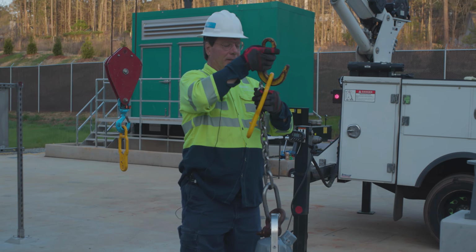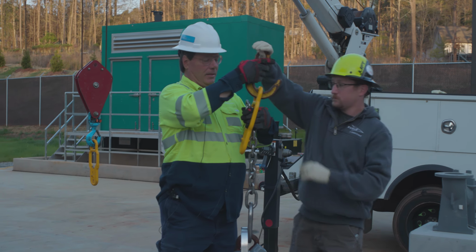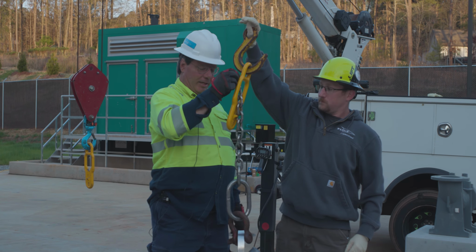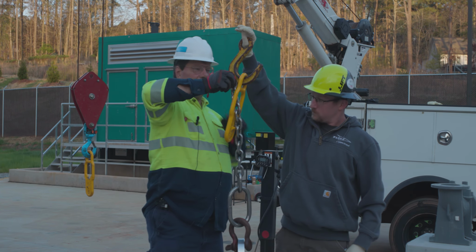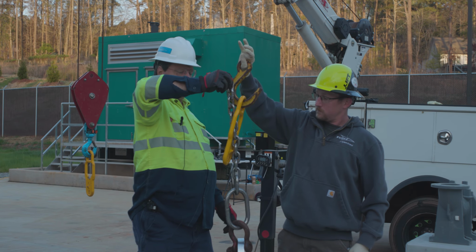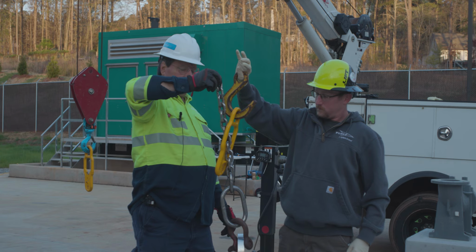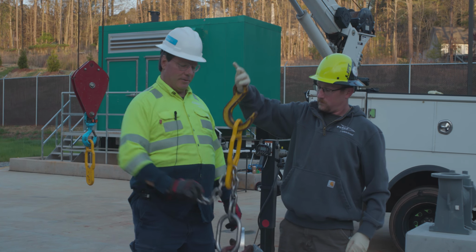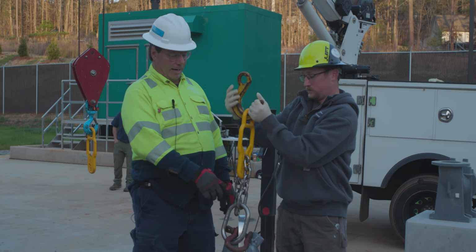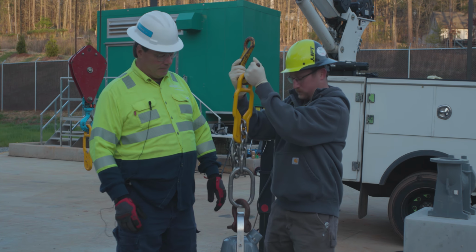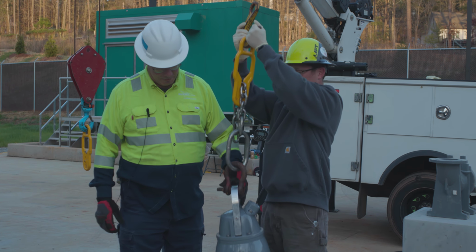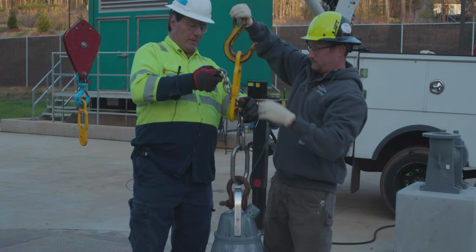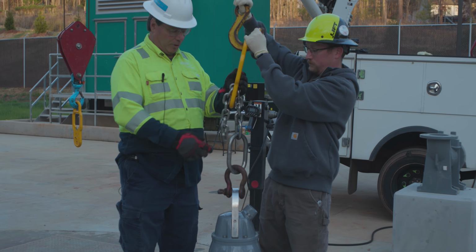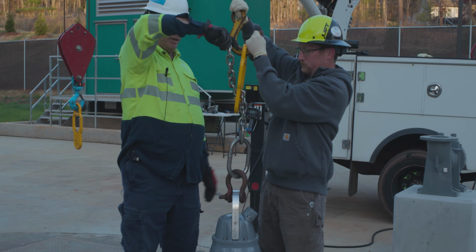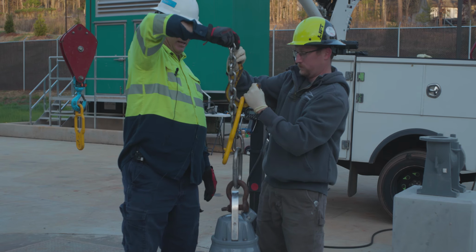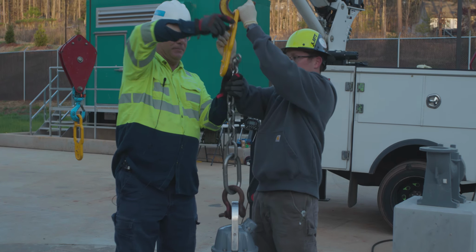This latch here, can you hold this for me? There's a string that's connected to the top, and when we lower the crane down, it's going to lower this chain sling device to a point where we can loosen the string, and then this will grab the chain hoist. When we lift the crane back again, it'll be able to pull the pump out of the well. And when we go to put it back down, we'll hold the string tight, we'll loosen it, and then he'll be able to lift it right back up again.